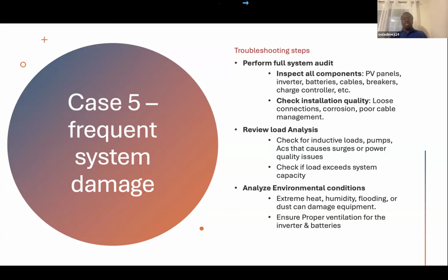Poor cable management. Then you review your load analysis and check for inductive loads, which most times are the culprits here: the pumps, the ACs, that cause surges or power quality issues. Sometimes they send this transient power that causes problem feedbacks to your solar system. Check if load exceeds system capacity.